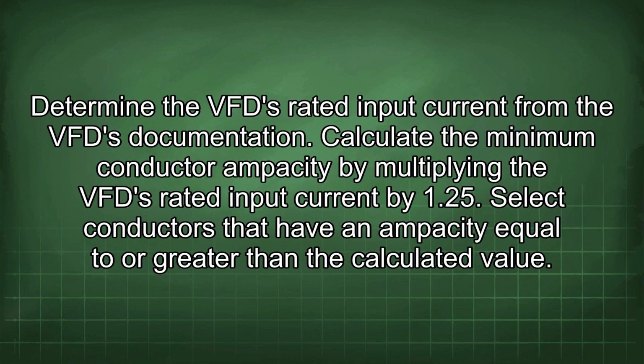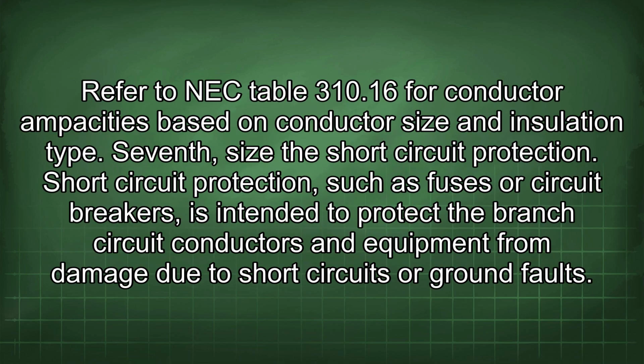Determine the VFD rated input current from the VFD documentation. Calculate the minimum conductor ampacity by multiplying the VFD rated input current by 1.25. Select conductors that have an ampacity equal to or greater than the calculated value. Refer to NEC Table 310.16 for conductor ampacities based on conductor size and insulation type.